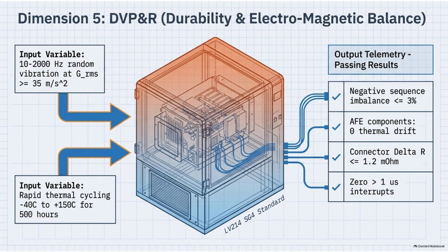For 500 continuous hours. And the validation metrics are microscopic. They monitor the current imbalance between the 3 phases. It cannot drift above 3%, proving those class 1 thin film resistors haven't shifted due to the thermal shock. The micro-resistance of the robotic busbar joints cannot increase by more than 1.2 milliohms despite 500 hours of violent shaking. It's a true torture test. And most astoundingly, they monitor the high-speed data signals. Not a single electrical signal can drop out for more than 1 microsecond.